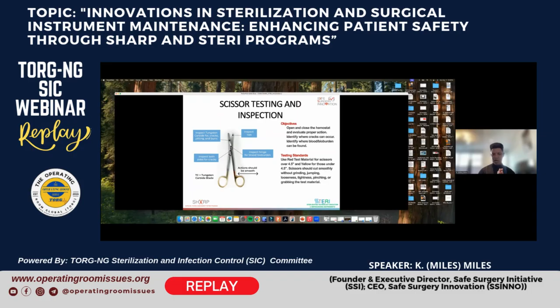You also want to slide down to look where the screws meet and make sure that there are no cracks in that area. Normally, when it comes to surgical instruments, if you have a screw or any type of piece where two parts of an instrument meet together, that's normally the stress point, and that's where you're more likely to see cracks and things like that. A good way to determine if an instrument has any cracks in it is to look for signs of rust. Rust and staining normally mean there may be a crack on that instrument.